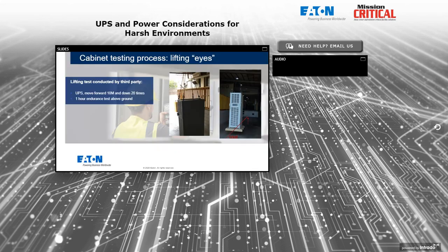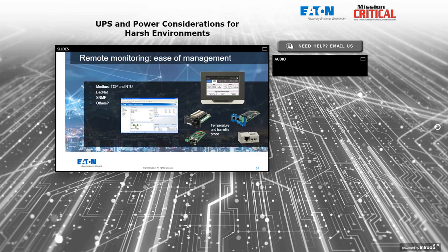We talked about lifting eyes before. Here's a good picture showing what we're talking about here, where we have eye bolts in the top of the UPS. And that usually means the frame of the UPS is a welded frame as opposed to a bolted frame, especially if that UPS contains heavy things like batteries. But the client says, look, I don't have provision for fork trucks to come and move this around on a pallet underneath the UPS. I need to lift it with my crane. So those types of requirements are common as well, much more so than they would be for IT equipment.